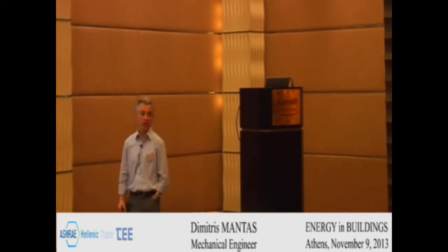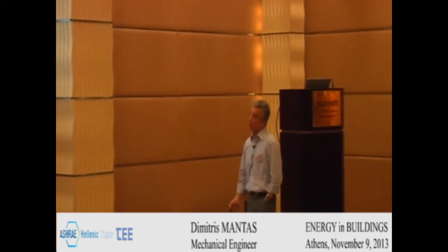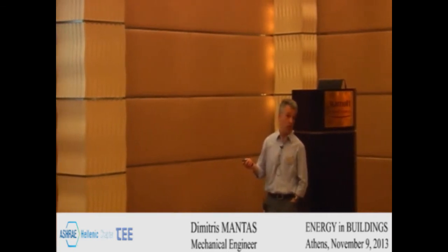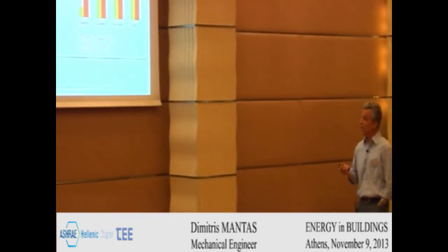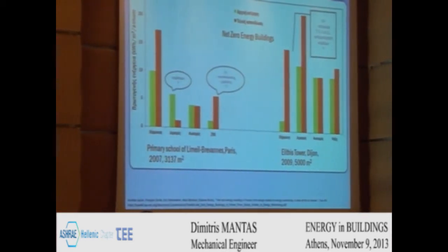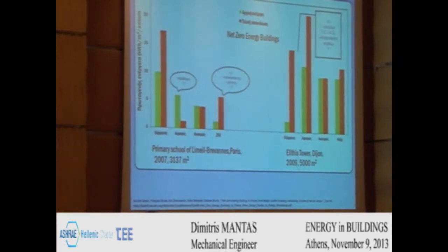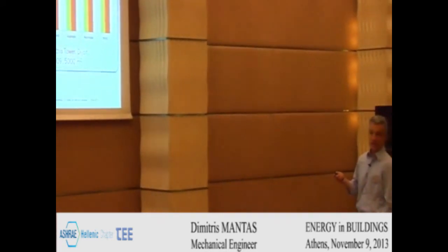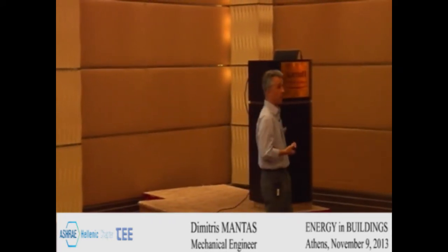So if we go back to the previous slides to look at the two indicative buildings, the school has much lower ventilation than planned. The children, the occupants, are actually playing with the windows, and we increase the heating loads since the automatic system does not work.